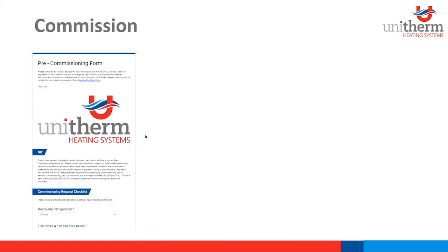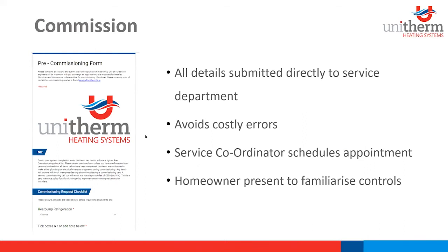Then on commissioning, we have a pre-commissioning form. It's filled out by the installer, and it makes sure the work is carried out as per Uni-Therm schematics and Uni-Therm's design. As I said, we have technical support there as well, so if there's ever any issues on site or anything, we're only a phone call away, or we can come out on site as well. So we supply all compliance documentation for all our projects, on-site commissioning of the heating system, and we then produce the commissioning certificate. So the homeowners are present, and we can run through optimal operation there as well. The service engineers run through optimal operation and best efficiency practice for the system installed.